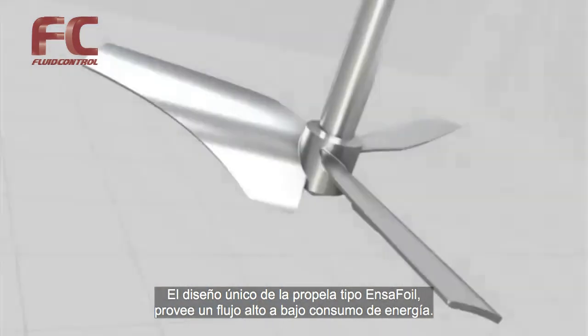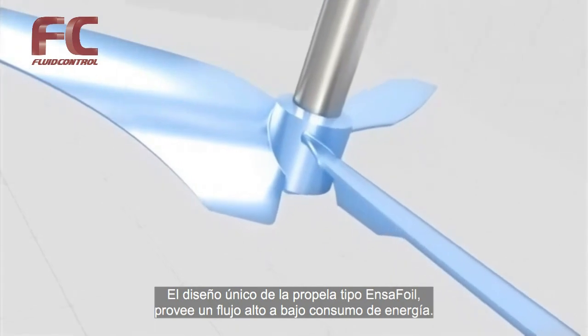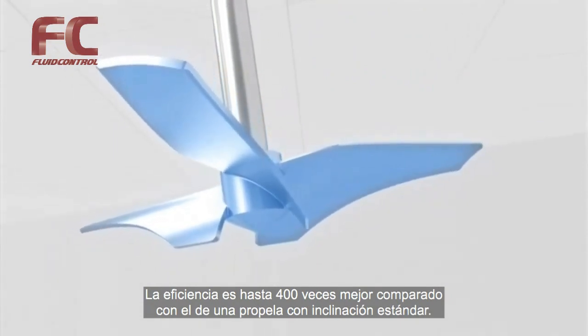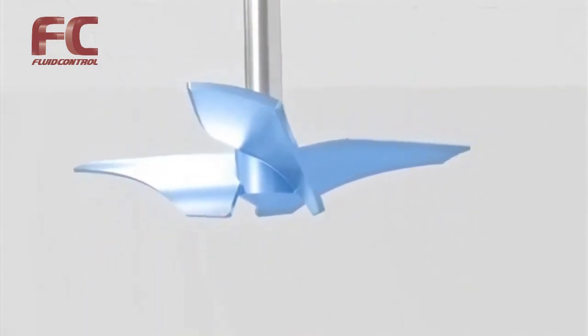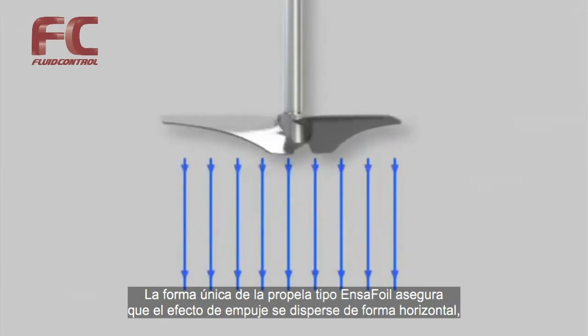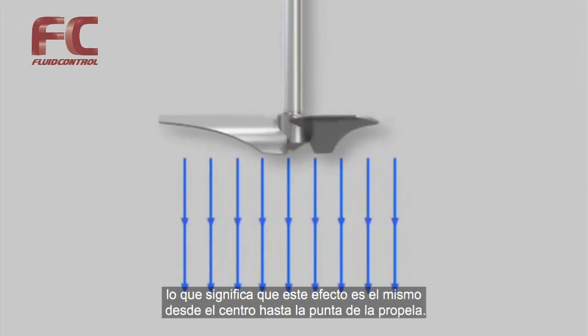The unique shape of the energy-saving EnsaFoil propeller provides a very high flow rate at low energy consumption. The efficiency is up to 400% better than for a propeller with blades of standard pitch. The unique shape of the EnsaFoil propeller ensures that the pump effect is spread out evenly, meaning the pump effect is the same from the hub to the tip of the propeller.